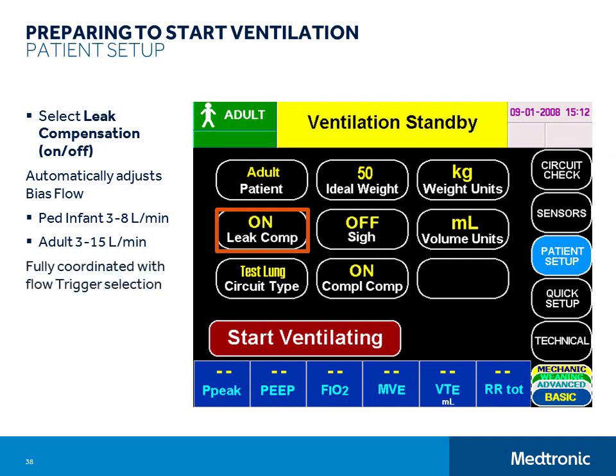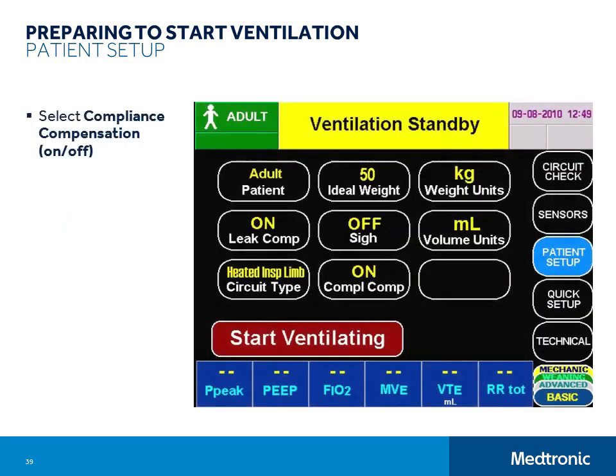And finally, set the compliance compensation to on or off. When compliance compensation is turned on, the ventilator automatically compensates for delivered volume loss due to breathing circuit compressibility during every volume-controlled mandatory breath, using the compliance compensation factor that was measured during the most recent circuit check.